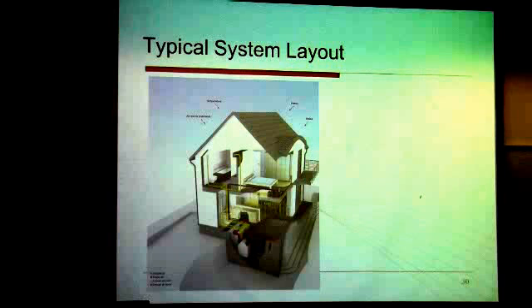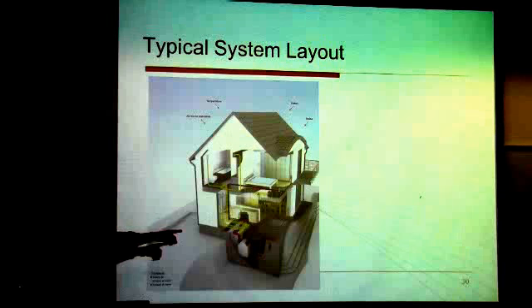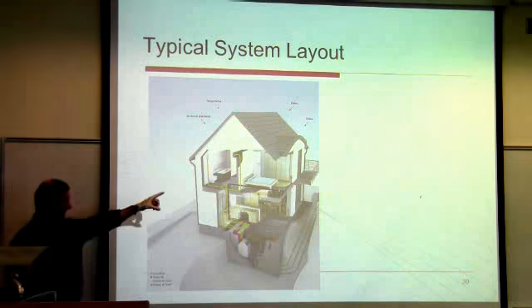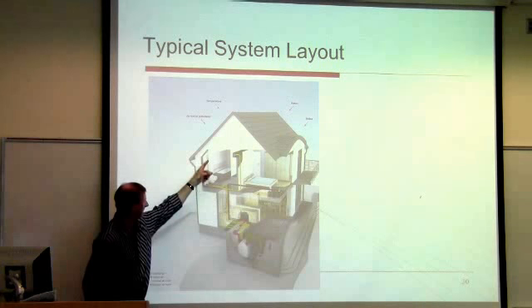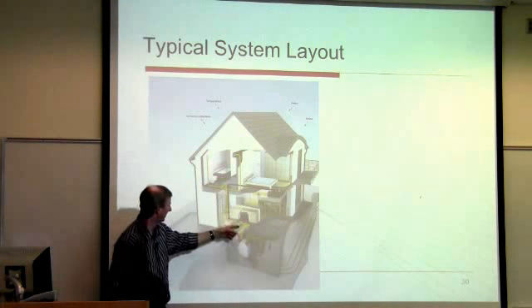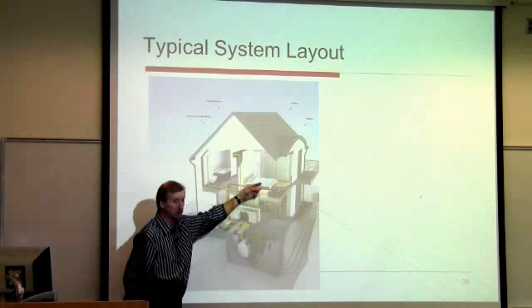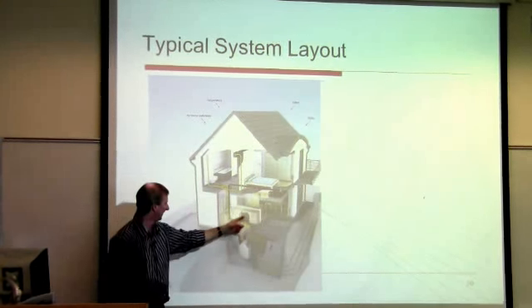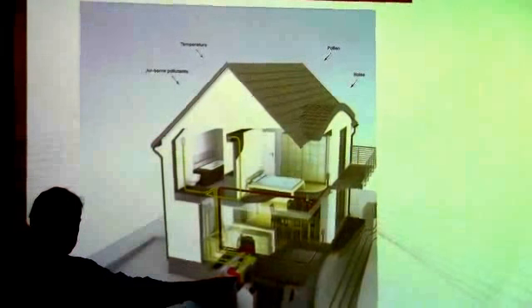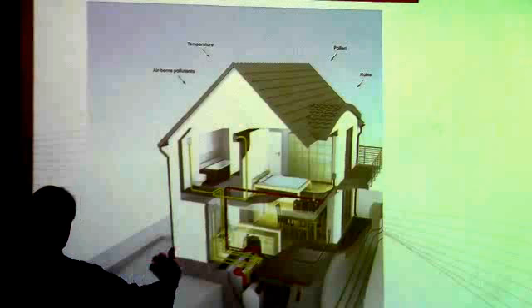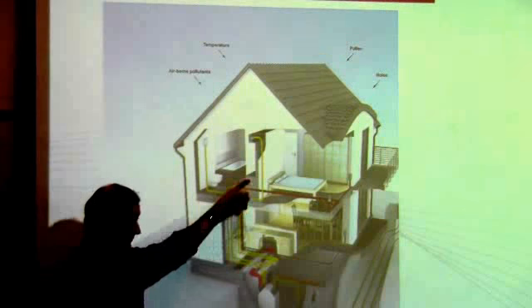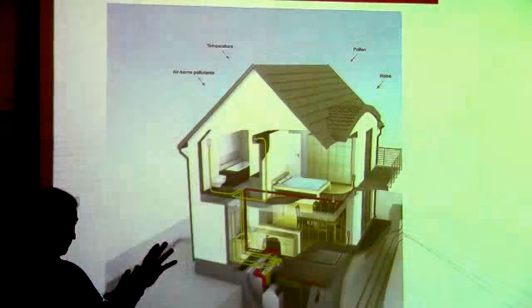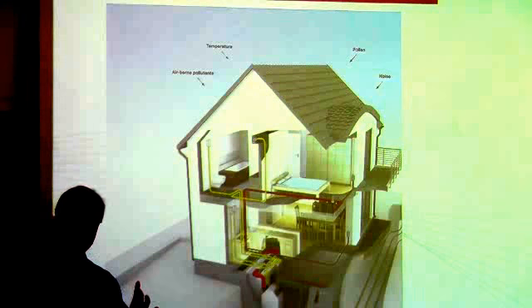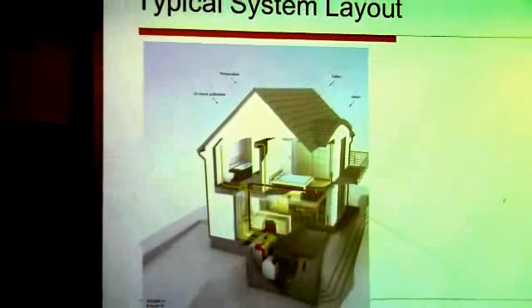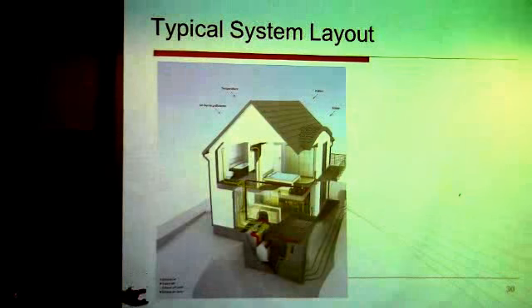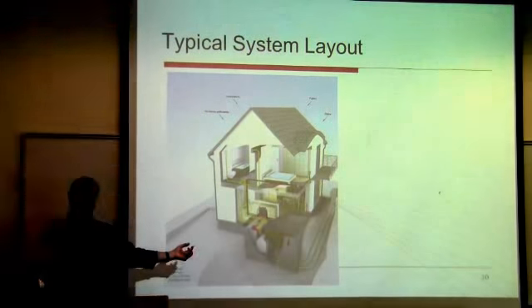Getting back to a typical system layout, this shows the yellow lines are return lines. They go back to an HRV down here. So it's coming from the bathroom and the kitchen area, and then the red lines are supplying the living room and bedrooms. And then here, you just have a distribution box, so you have maybe 6 or 7 inch duct going up to a distribution box, then this 3-inch ducting will come out of it and run to all the other areas. So you can use conventional ducting, but most conventional ducting is made for conventional systems which are flowing 1,000 CFM for a central forced air system, where this is flowing 10% of that, or 100 CFM, 60 CFM.